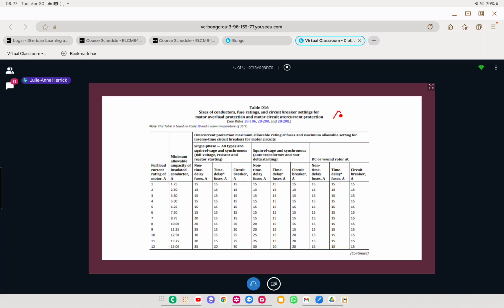So let's say you have a FLA of 2 amps and you have the circuit breaker for a squirrel cage motor. You know it's 250%. And then you go to Table D16 and you go down to find your circuit breaker. This already does it for you. So you don't have to do any motor math or motor calculations. D16 already does all of your calculations for you, not only for the ampacity of the insulated conductor based on continuous duty, but also for all of your overcurrent. So you don't have to do any math. This is an extraordinarily handy table when you're in a hurry.